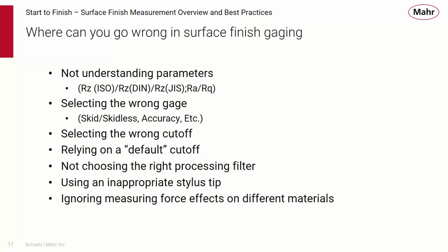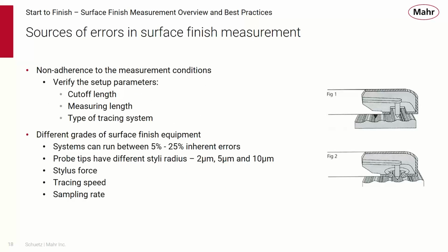Sometimes you can select the wrong gauge, whether it be a skidless gauge or a skidded system, what the accuracy is, those can affect the readings. Selecting the wrong cutoff, the sampling length, relying on a default cutoff, letting the machine do all the work. There are also things like not choosing the right processing filter, using an inappropriate stylus tip because tips do come in different radii, and ignoring measuring force because that can have effects on different materials. So non-adherence to the measurement conditions.